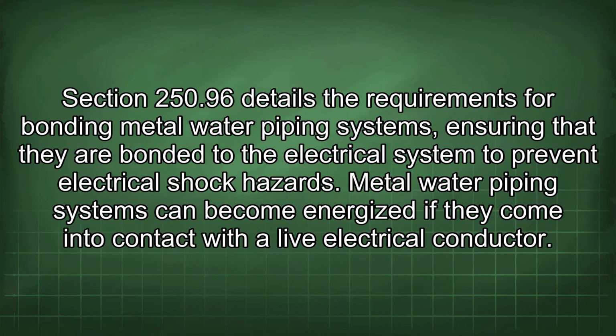Section 250.96 details the requirements for bonding metal water piping systems, ensuring that they are bonded to the electrical system to prevent electrical shock hazards. Metal water piping systems can become energized if they come into contact with a live electrical conductor.